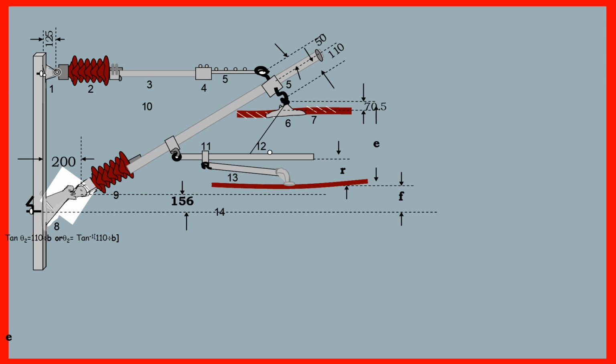The suspension clamp hole center to the contact wire center is 70.5 millimeter. Encumbrance, we know, is the axial distance of contact and catenary wire. It is a variable quantity, as per the height of the contact wire, because in overlap structure the encumbrance is reducing. Normally in normal OH it is 1.4 or 1400 millimeter.